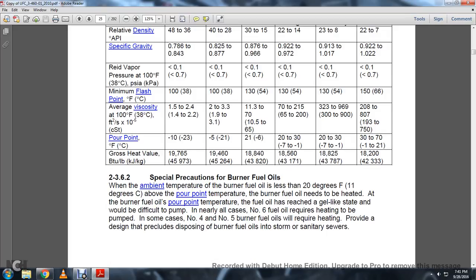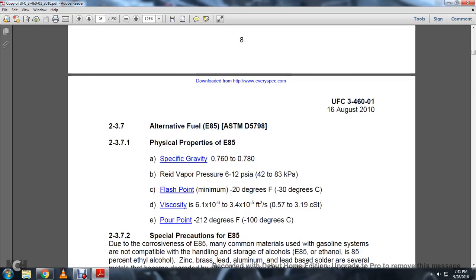2.3.6.2 Special precautions for burner fuel oils. When the ambient temperature is less than 20 degrees Fahrenheit above the pour point of the burner fuel oil, the oil needs to be heated. At the pour point, the fuel reaches a gel-like state and would be difficult to pump. In nearly all cases, number 6 fuel oil requires reheating to be pumped. In some cases, number 4 and number 5 burner fuel oils require heating. Provide a design that precludes disposing of burner fuels in storm and sanitary sewers.